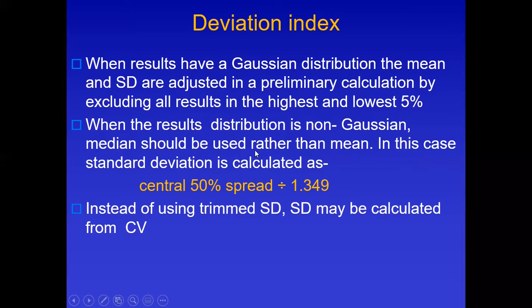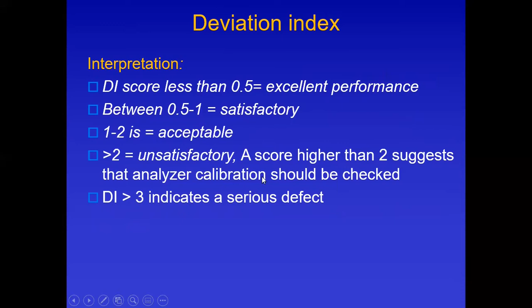How do we interpret the result of the deviation index? When the deviation index is less than 0.5, it means excellent performance. Between 0.5 and 1, satisfactory performance. Between 1 and 2, acceptable performance. More than 2 is unsatisfactory and suggests that analyzer calibration should be checked. And a deviation index of more than 3 indicates a serious defect.